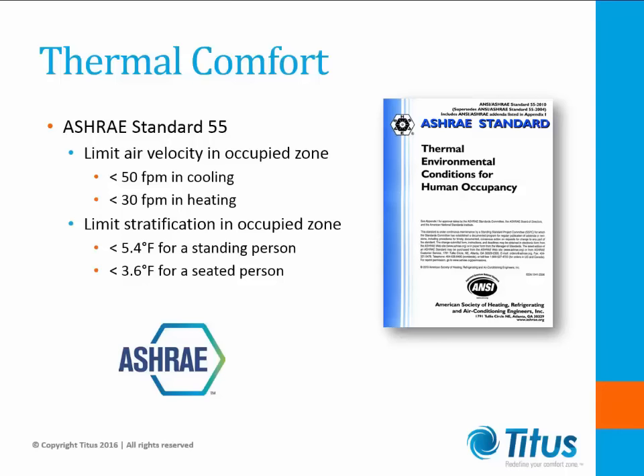Stratification usually carries a negative connotation, but if we're careful and control the level of stratification, we can use it to our advantage when designing UFAD systems. You know that you have excessive temperature stratification when you sit down and feel cold, but stand up and feel like you've got a fever. Standard 55 recommends no more than a 5.4 degree delta T between the neck and ankle region of a standing person, which translates into a 3.6 degree Fahrenheit delta T for a seated person. So long as we can limit velocities and stratification in the occupied zone, we should be able to deliver good thermal comfort.